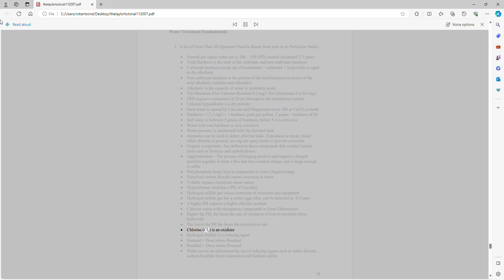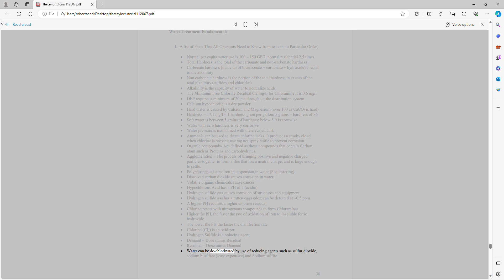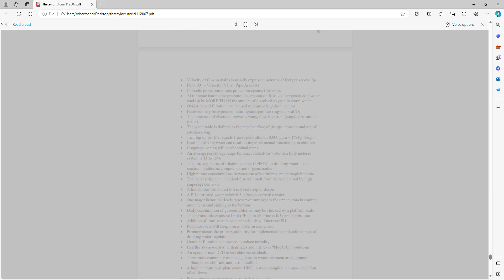Chlorine (Cl₂) is an oxidizer. Hydrogen sulfide is a reducing agent. Demand equals dose minus residual; residual equals dose minus demand. Water can be dechlorinated by use of reducing agents such as sulfur dioxide, sodium bisulfite (least expensive), and sodium sulfite.